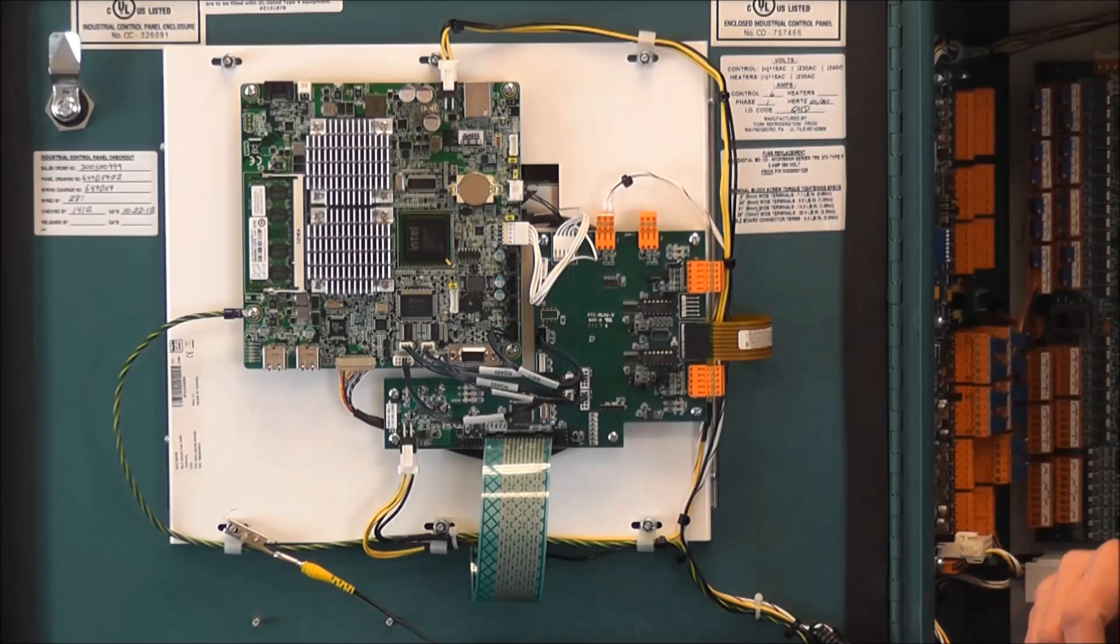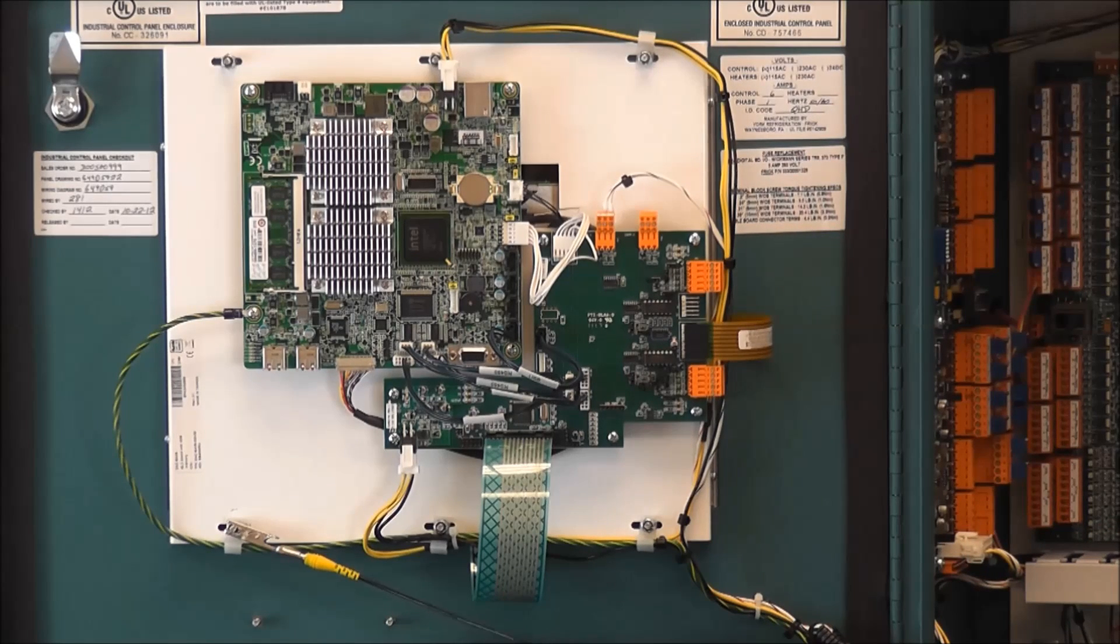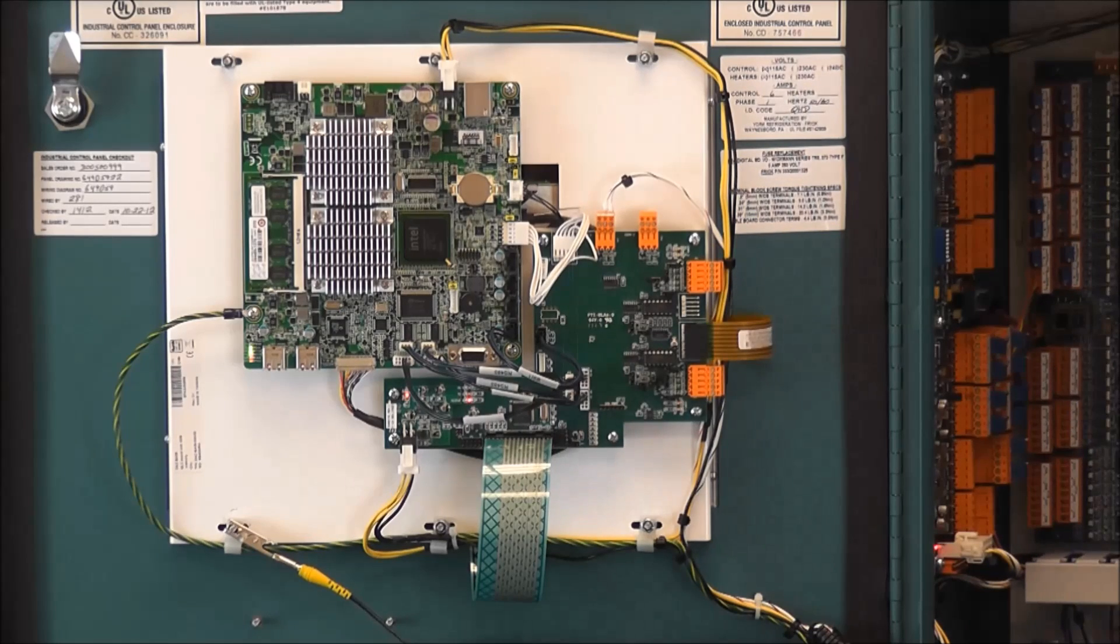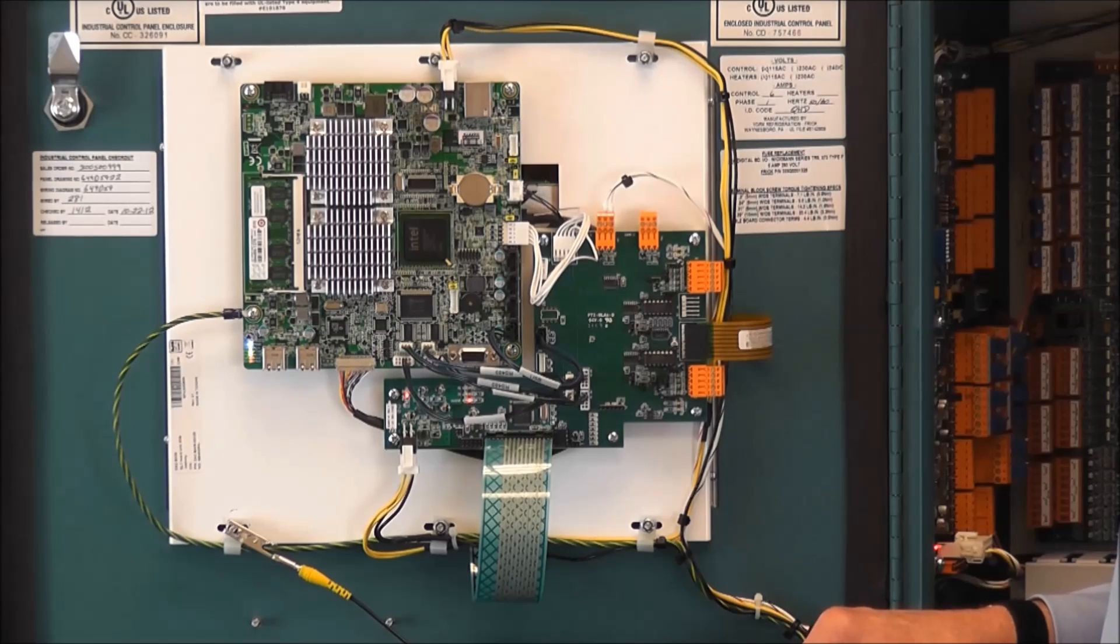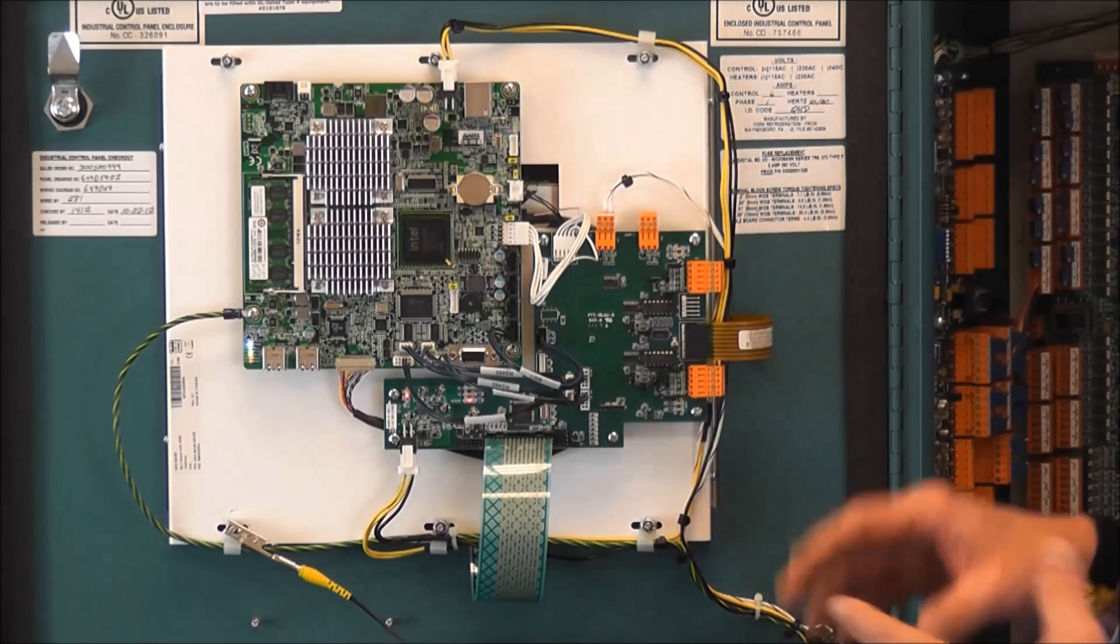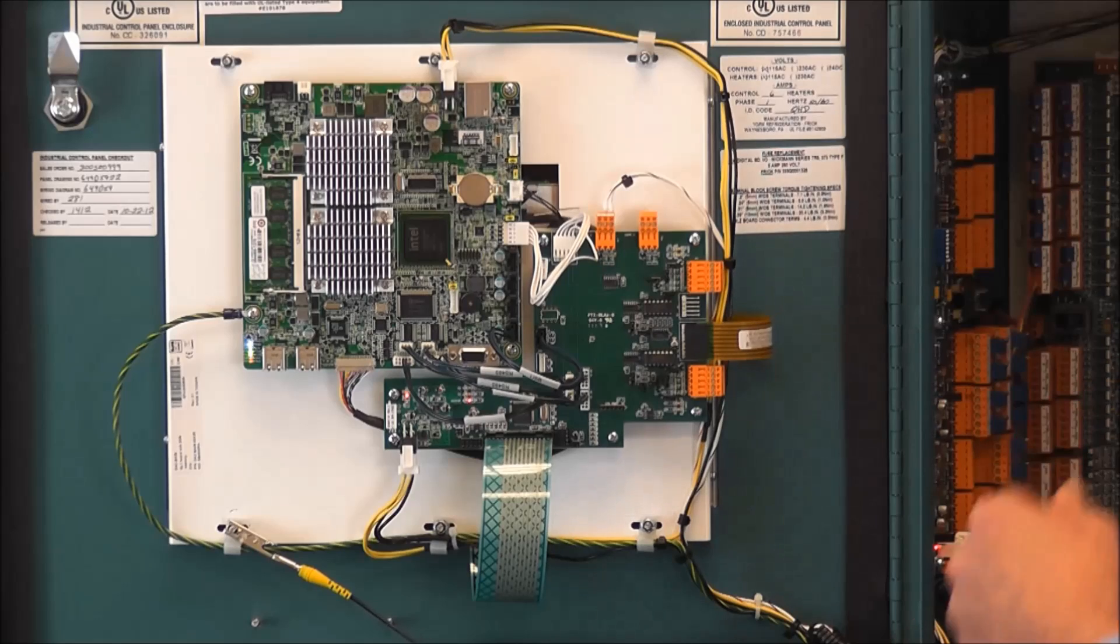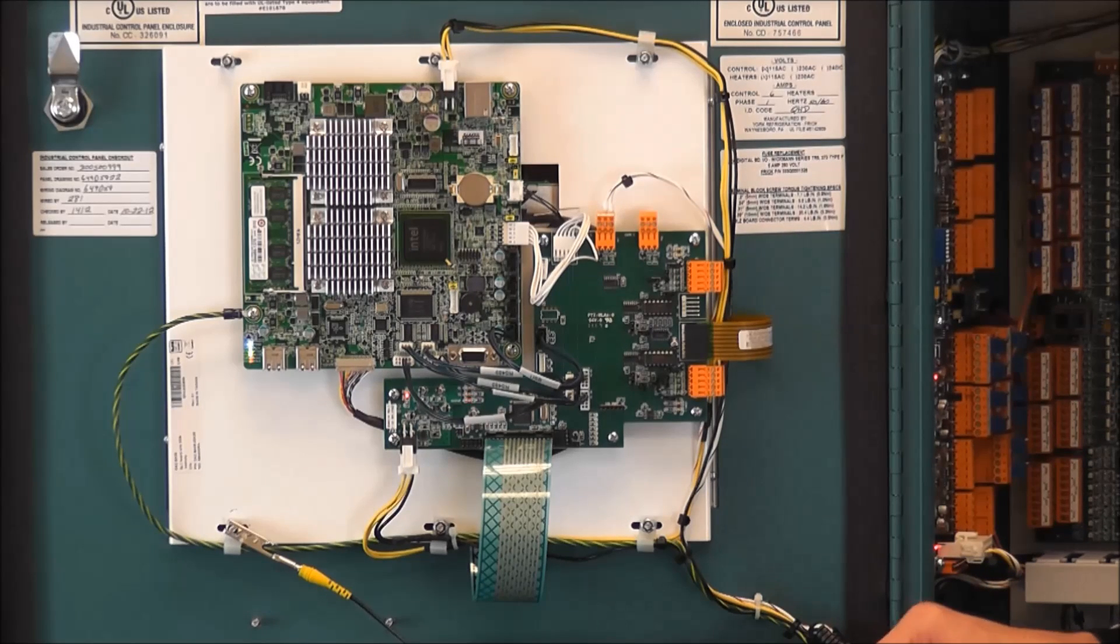Now the next step we want to do is we want to reinstall our USB thumb drive. With the type of processor we have, the USB thumb drive can only be mounted once the processor is fully booted up. Now from the outside, we have a couple of things that we can tell basically that it has booted once the RX-TX lights on the analog and digital board starts to flash.